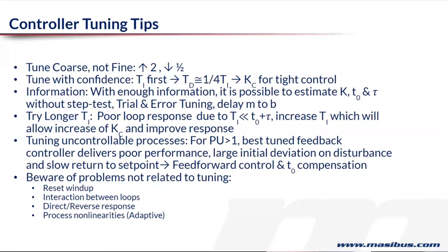Actually, if you have good enough information about the process, it is possible to estimate all three terms: the process gain, the process dead time, and the process time constant. Like in an electrical circuit, as I told you, RC is the time constant. So if I know R and I know C, I can calculate the time constant. So even without doing a step test, you should be able to estimate the time constant and also the gain.